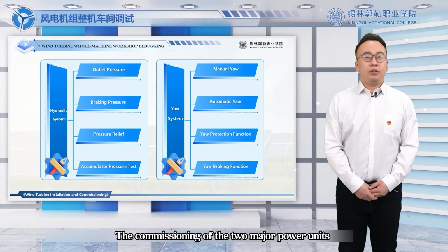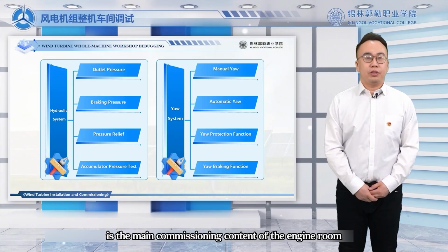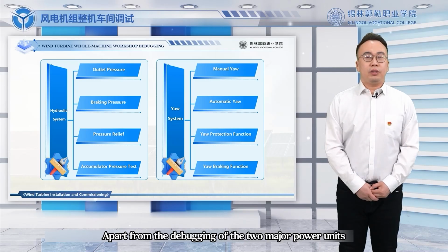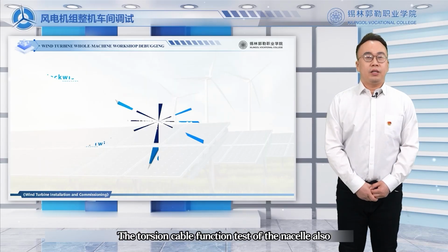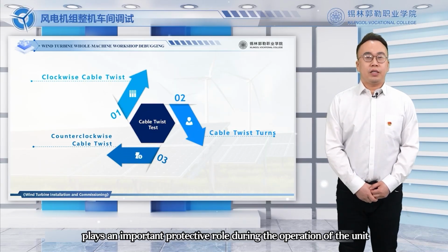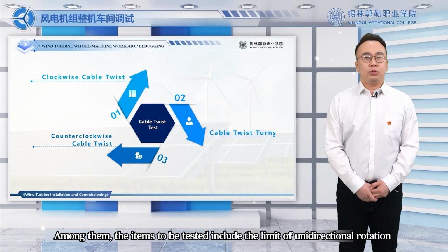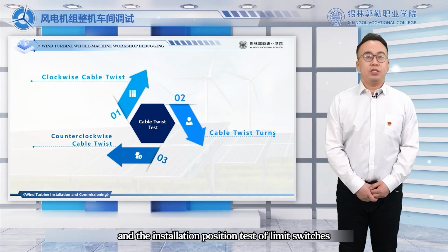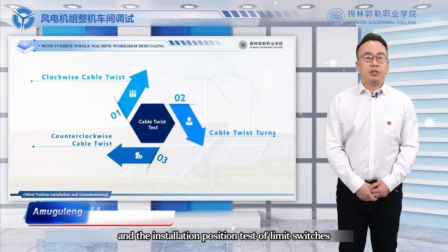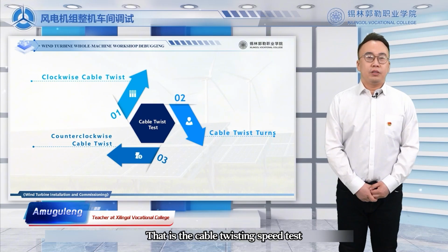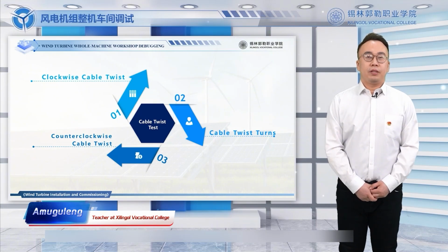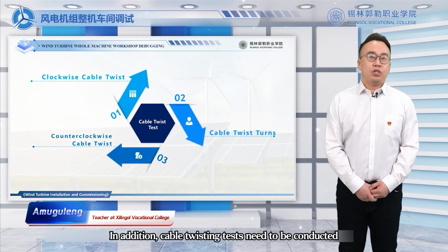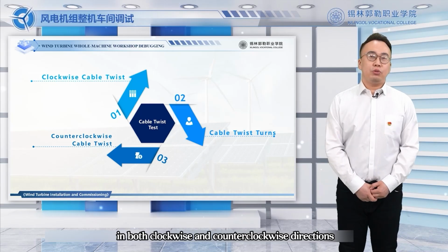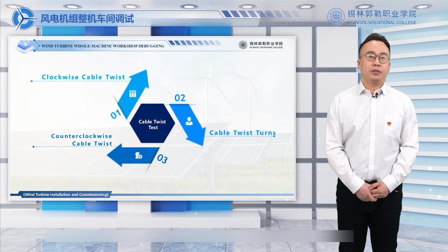The commissioning of the two major power units is the main commissioning content of the engine room. Apart from debugging the two major power units, the torsion cable function test of the nacelle also plays an important protective role during operation. Items to be tested include the limit of unidirectional rotation and the installation position test of limit switches, that is, the cable twisting speed test. In addition, cable twisting tests need to be conducted in both clockwise and counterclockwise directions.